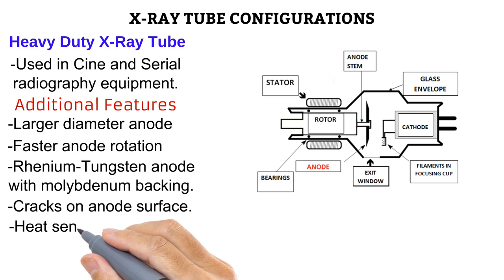Lastly, the temperature of the anode is monitored with a heat sensor that is normally placed behind the anode. This sensor is connected to certain lights which indicate to the operator when the tube is too hot to be operated. This helps to prevent damage to the tube from overheating.